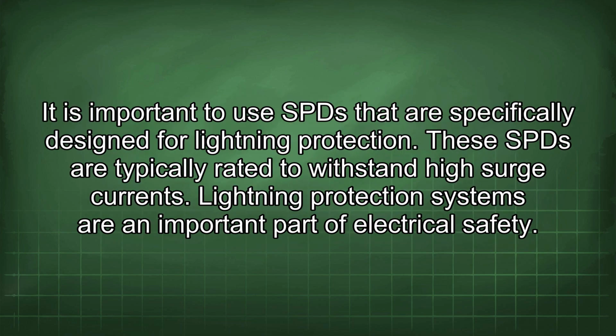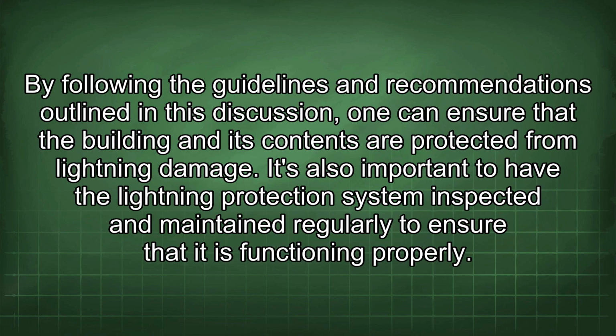It is important to use SPDs that are specifically designed for lightning protection. These SPDs are typically rated to withstand high surge currents. Lightning protection systems are an important part of electrical safety. By following the guidelines and recommendations outlined in this discussion, one can ensure that the building and its contents are protected from lightning damage. It's also important to have the lightning protection system inspected and maintained regularly to ensure that it is functioning properly.